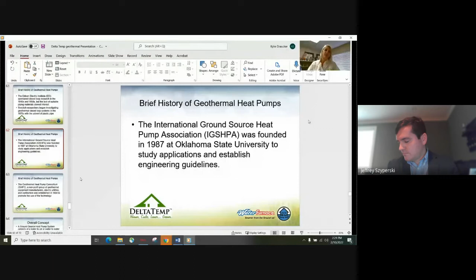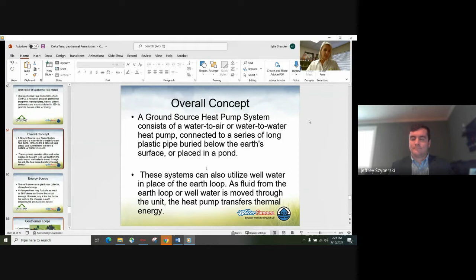So what is geothermal? What's the overall basic concept, and how can it be installed into a current residential home? A ground source heat pump system consists of a water-to-air or water-to-water heat pump, connected to a series of long plastic pipes buried in the Earth's surface or placed in a pond. These systems can also be utilized through well water placed in the earth loop, and as fluid from the earth or well water is moved through the unit, the heat pump transfers that thermal energy.